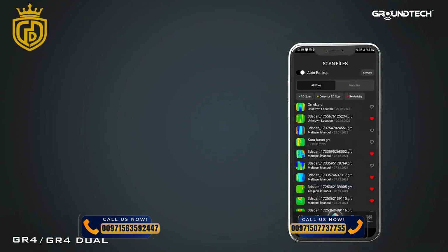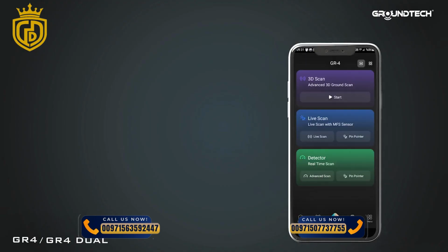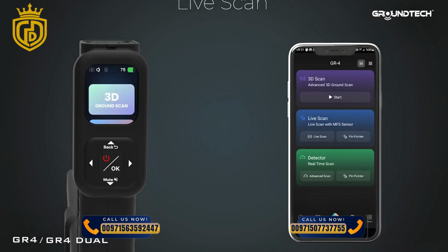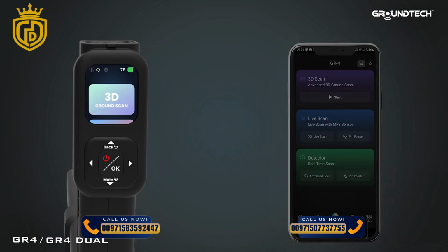Let's move on to the next scanning mode of the device. Live scanning mode. Live scanning is the 2D scanning mode that allows you pinpoint detection. In this mode, it is possible to scan without being confined by any specific order and by using both the display of the device and the G-Portal mobile app. To be able to use the live scanning mode, you need to make sure that the MFS sensor is attached to the device. We'll first take a look at the device interface.